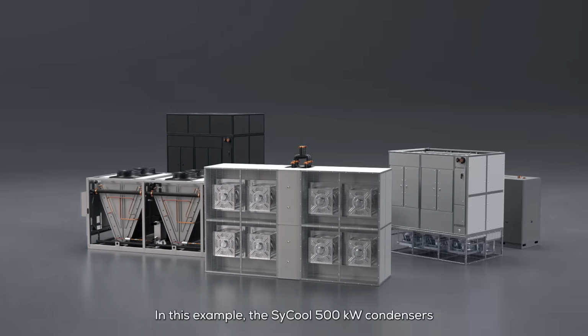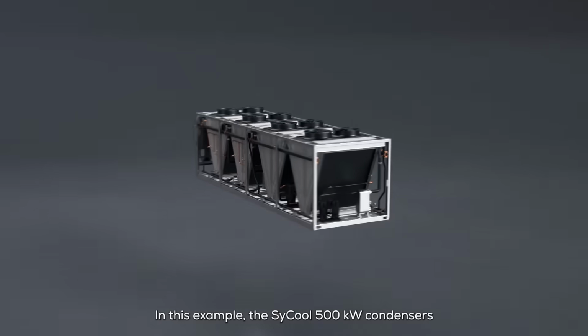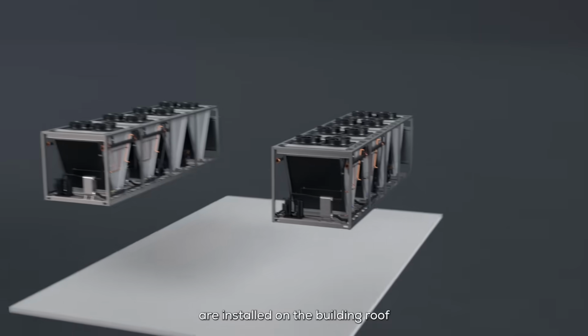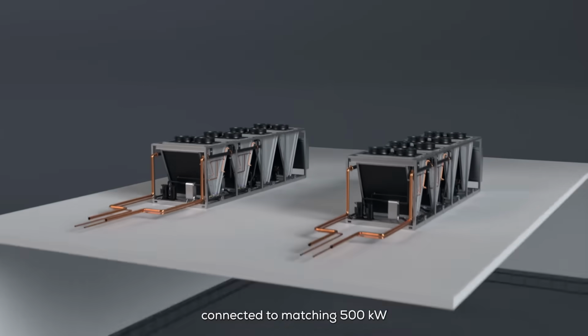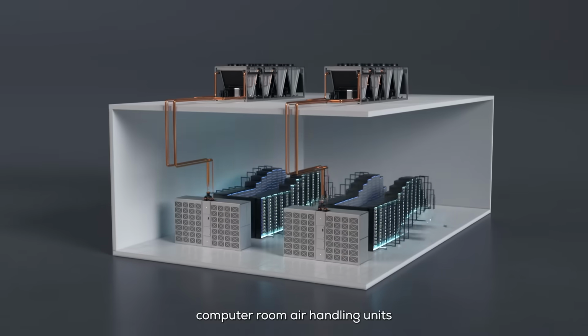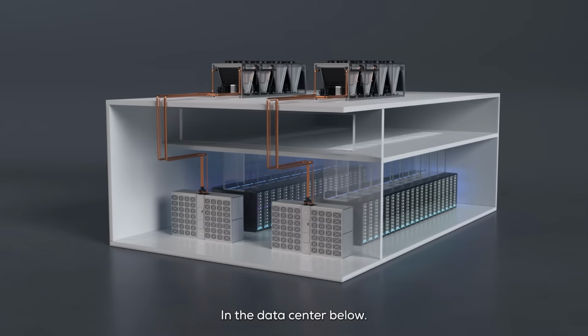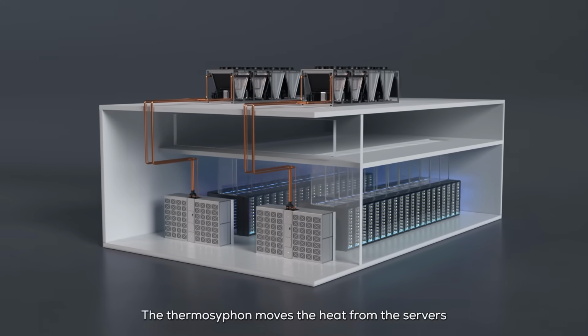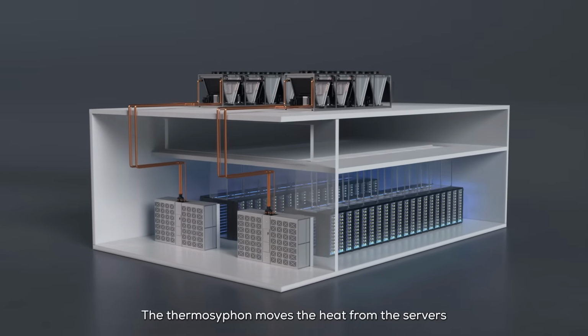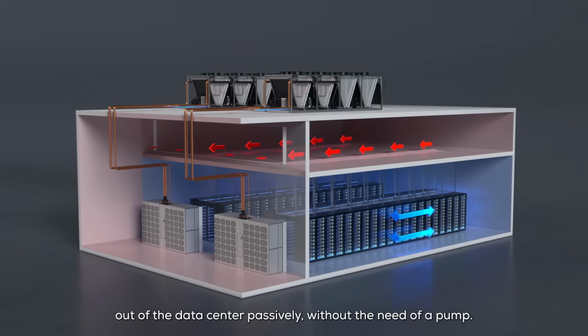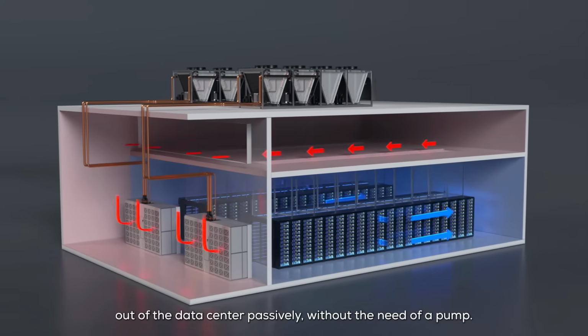In this example, the SyCool 500 kilowatt condensers are installed on the building roof, connected to matching 500 kilowatt computer room air handling units in the data center below. The thermosiphon moves the heat from the servers out of the data center passively, without the need of a pump.